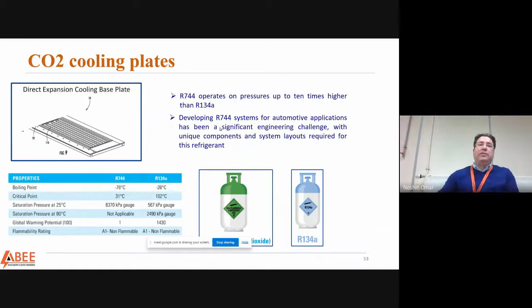The global warming potential for R744 is around 1, compared to roughly 1,430 for the other one, which is very problematic. However, the saturation pressure is very high, so there are different pros and cons to take into account, and it's not easy to handle. R744 operates at pressures at least 10 times higher than the classical refrigerant, which requires a lot of engineering and optimization work, particularly regarding safety and component selection.